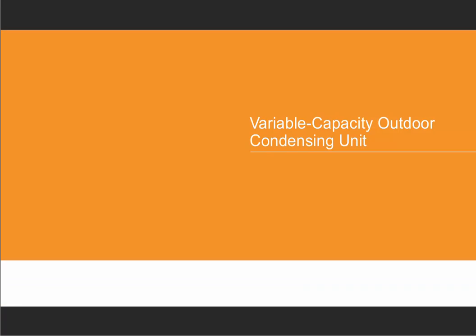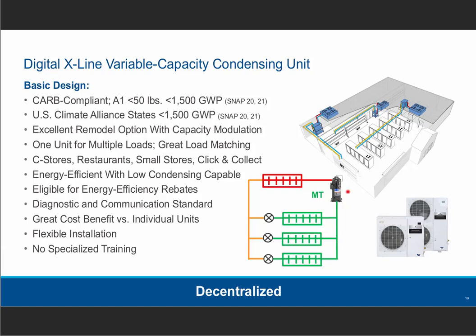There's some options there. Now take that a step further, and it starts to open up remodel applications. Take a standard condensing unit and add variable capacity to a single unit like that, and all of a sudden that opens up multiple evaporator use for a single condensing unit with a single compressor. So it gives you a little bit more flexibility in remodels of old facilities. You may be replacing three smaller condensing units with one. And if the proximity of the unit is such that you can keep your charge low, then your applications start to grow. You can use them in more regions, following the guidelines of refrigerant allowability depending on where you are. So it is an excellent remodel option.